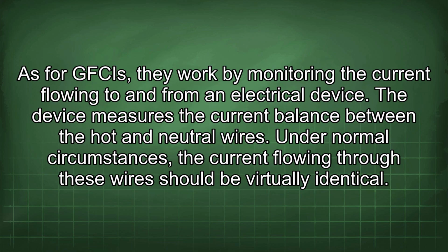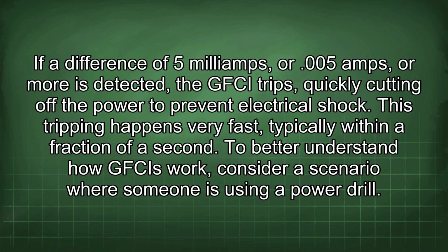As for GFCIs, they work by monitoring the current flowing to and from an electrical device. The device measures the current balance between the hot and neutral wires. Under normal circumstances, the current flowing through these wires should be virtually identical. If a difference of 5 mA or more is detected, the GFCI trips, quickly cutting off the power to prevent electrical shock. This tripping happens very fast, typically within a fraction of a second.